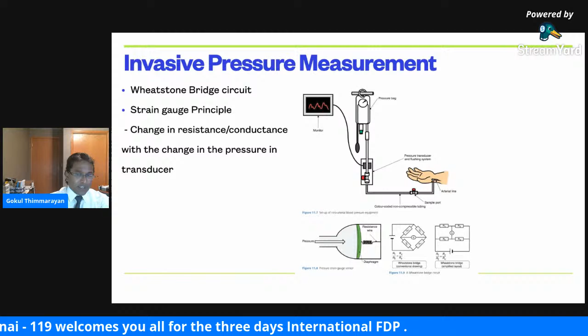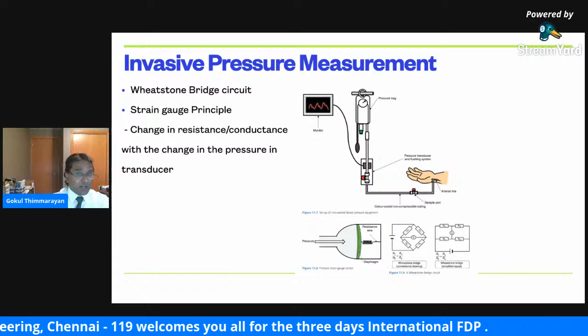But I thought of discussing this invasive pressure measurement, where an IV cannula is put inside the patient's artery, and it's connected to a tubing with fluid, which is connected to a transducer. And this transducer is connected to the monitor. And this transducer has a Wheatstone bridge, and it works on the principle of strain gauge. So every time the artery pulsates, this pulsation travels through the tubing. There's a change in the pressure in the tubing through the liquid column, and it pushes on the transducer. And when it pushes on the transducer, the change in the pressure creates a change in the resistance or conductance in the Wheatstone bridge. And this change with every pulsation is analyzed and it's given as a waveform and a number, giving the patient's blood pressure with every beat of the heart.